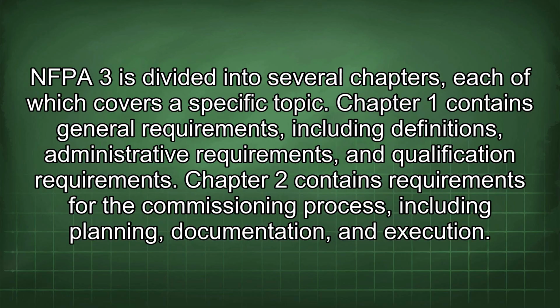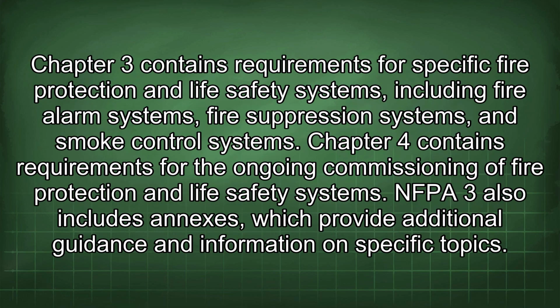NFPA 3 is divided into several chapters, each of which covers a specific topic. Chapter 1 contains general requirements, including definitions, administrative requirements, and qualification requirements. Chapter 2 contains requirements for the commissioning process, including planning, documentation, and execution. Chapter 3 contains requirements for specific fire protection and life safety systems, including fire alarm systems, fire suppression systems, and smoke control systems. Chapter 4 contains requirements for the ongoing commissioning of fire protection and life safety systems.